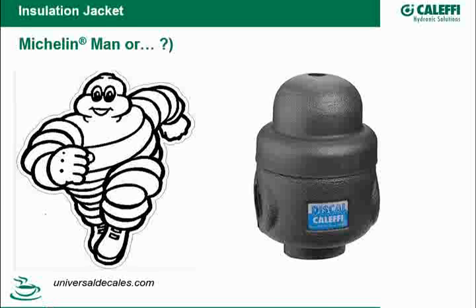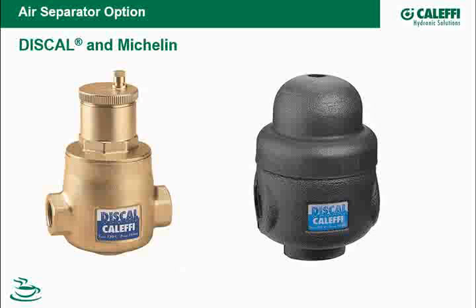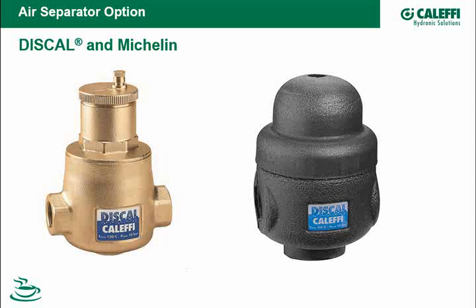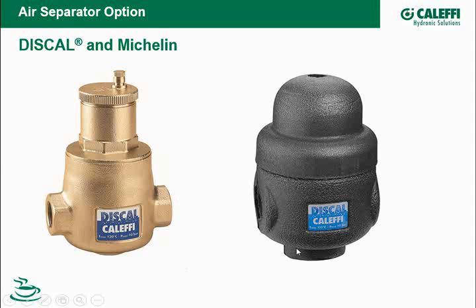Here you can see one for the DISCAL on the left, and of course the insulation shell that goes with it. We're selling it as an option, just so if people want to do that, if they're going to insulate the system. This one would work good for chilled water too, and we'll talk about this as we go on, but it's critical on a chilled water system that you don't have any exposed metal because that's going to condense, it's going to sweat, it's going to drip.